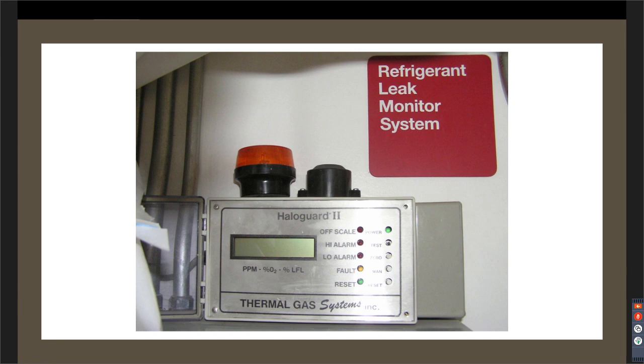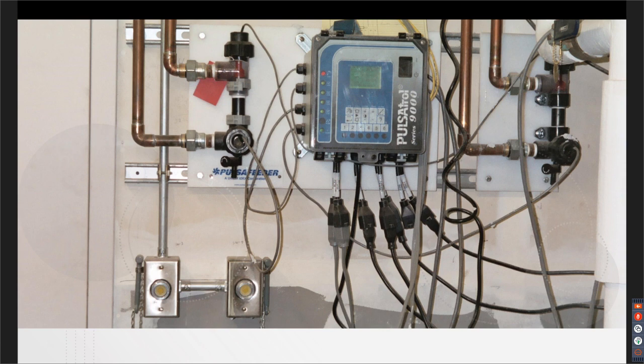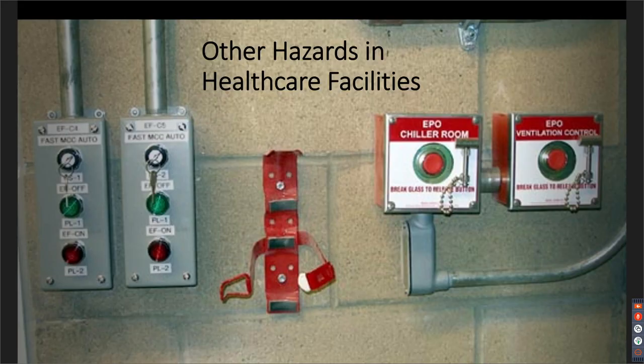The gas systems themselves are not all that unique. However, there is a code requirement that the power supply for the leak detection system be the same as is required for fire alarm systems. So I have to have the same style of circuitry as well as battery backup. This is probably not what the code had in mind with a bunch of receptacle style plug-ins.